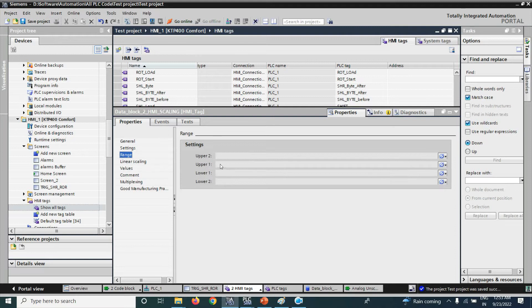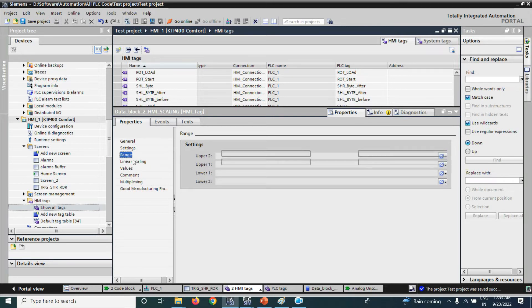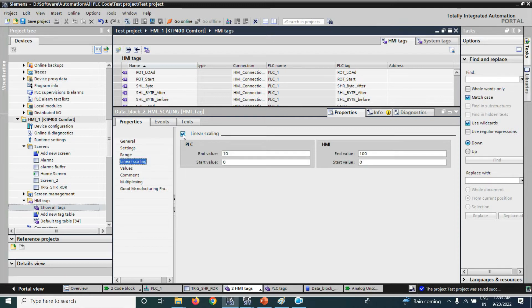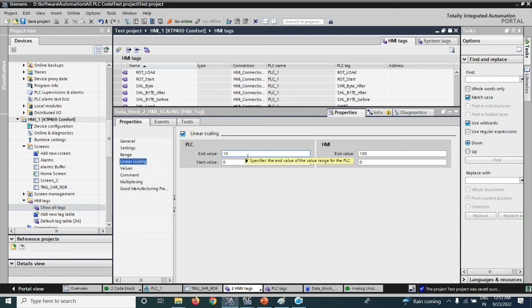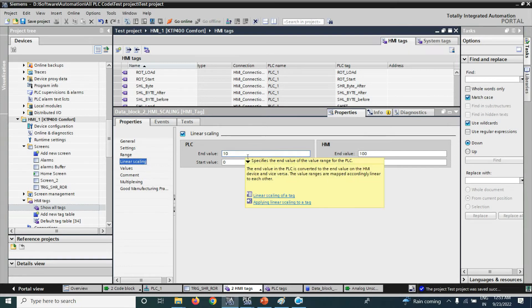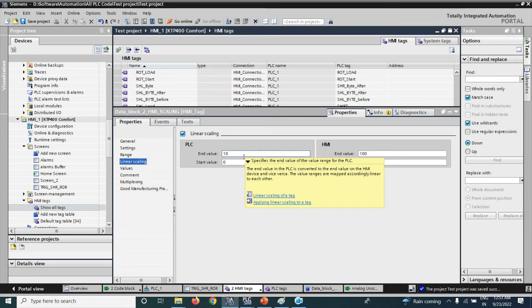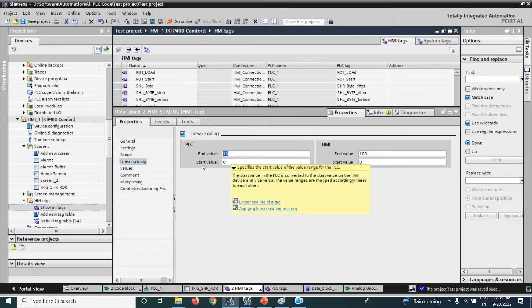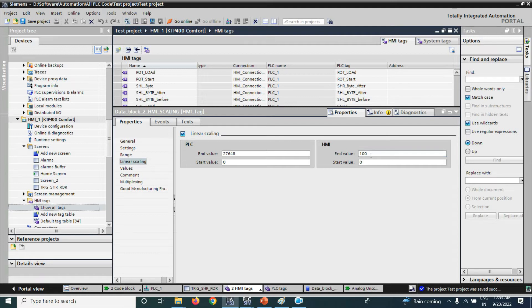Now, here you can see the range. Here, we will use the linear scaling function. Just select that linear, the checkmark, it will show. Here, we know that Siemens uses the integer value that is 27648 for the 20 milliamps and for 4 milliamps it will use 0. So, input value is 0, end value is 27648. And from HMI, we will use 0 to 100, end value 100.